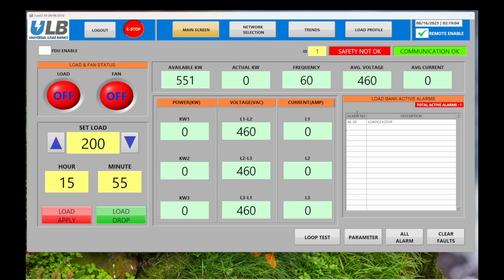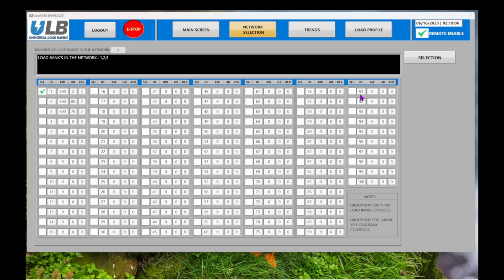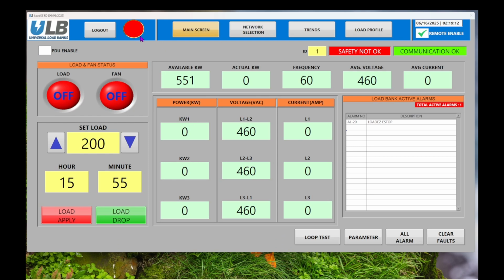Click on the ID to select which load bank you want to operate. In this case, we'll select ID 1. You can always return to this page by clicking Network Selection. From the main screen, you can monitor system status. To view active alarms, click All Alarm. To clear all alarms, press Clear Faults. You can also monitor real-time parameters for troubleshooting and diagnostics.